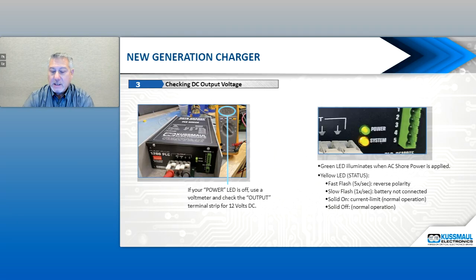On the second generation or newer charger, we know the green light will be illuminated if there's shore power applied. The yellow status light, if flashing 5 times per second - a very rapid flash - lets you know it's on but seeing reverse polarity somewhere, so double check that the wires are correct. If it's a slow flash, it's working but doesn't sense a battery. If both lights are on, that means it's in normal operation. If the system light is off, that doesn't mean it's bad - that also shows it's in normal operation.